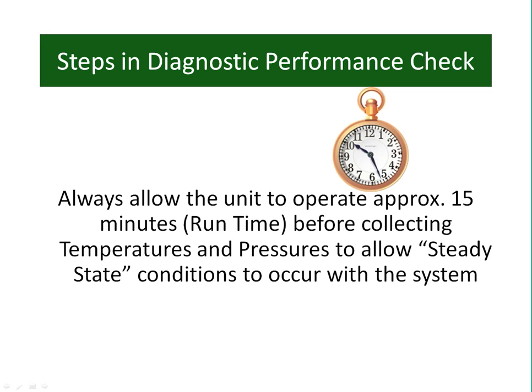If you rush to take these readings, you're not likely to get a representative condition of the air, because most of these systems are forced air systems. You won't get a real representation of what the air in that home truly is. The other area of concern is you want to make sure that the loop fluid has a chance to blend and circulate, and you're actually getting a true representation of what the loop fluid temperatures are, because those are what you want to check. What are the conditions that caused this fault or whatever brought you out there?